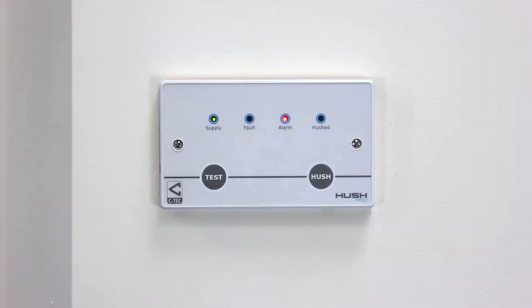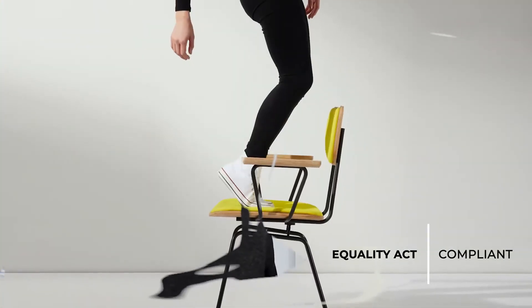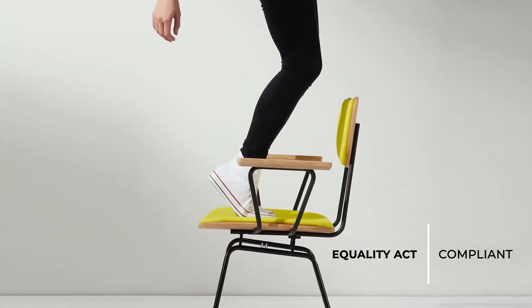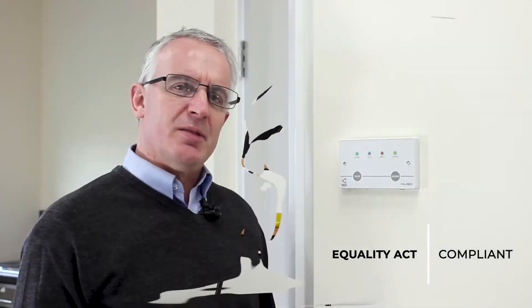In a Fire Level 1 condition, which is likely to be a false alarm, the dwelling sounders will sound and the building occupant can go to the controller and press the Hush button to silence the alarm while they investigate. As you can see, you can press the Hush button while standing at floor level without having to climb on a chair or a set of ladders. This means the system is safer and fully compliant with the Equality Act.